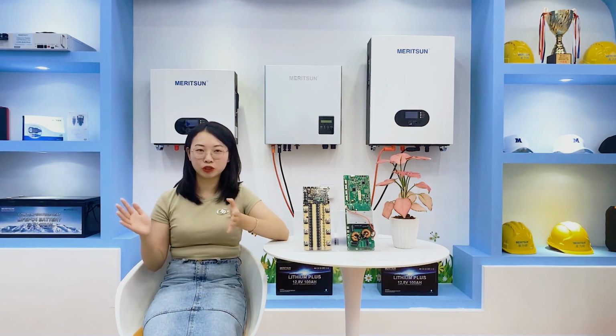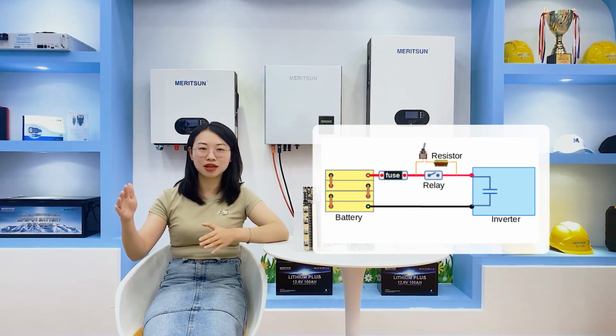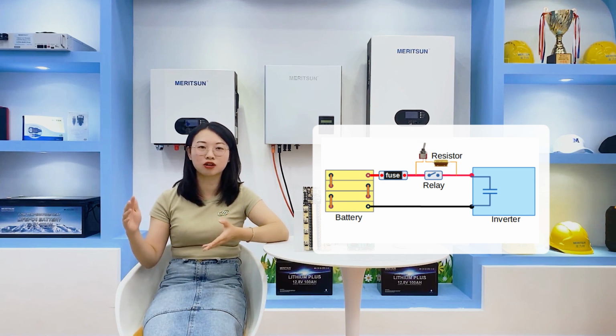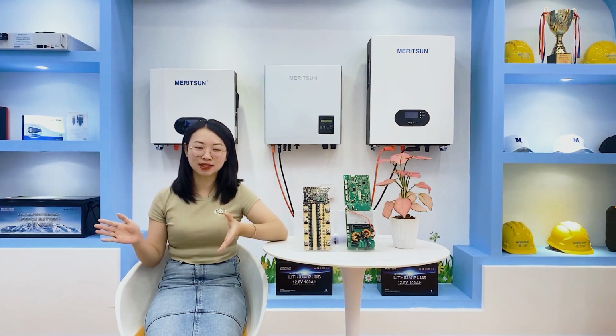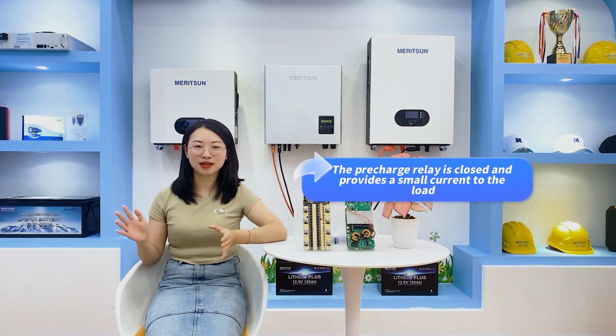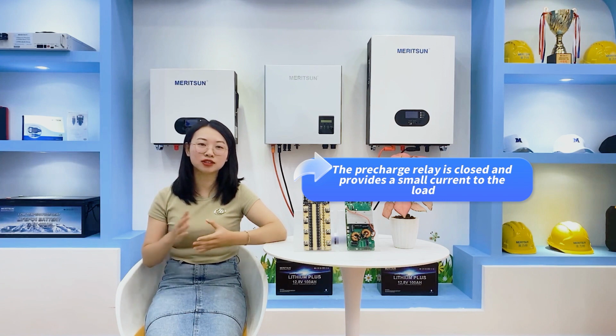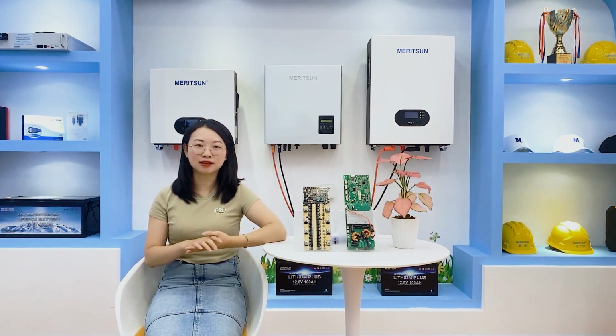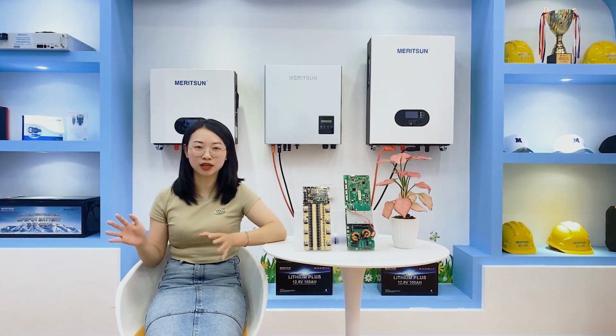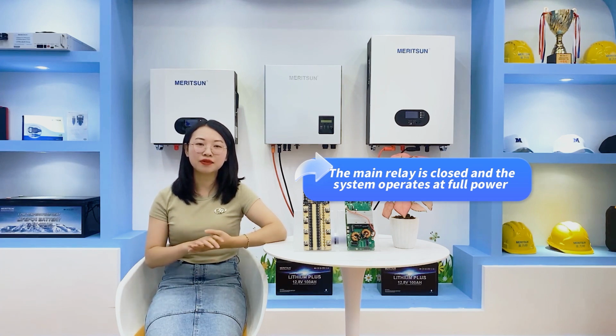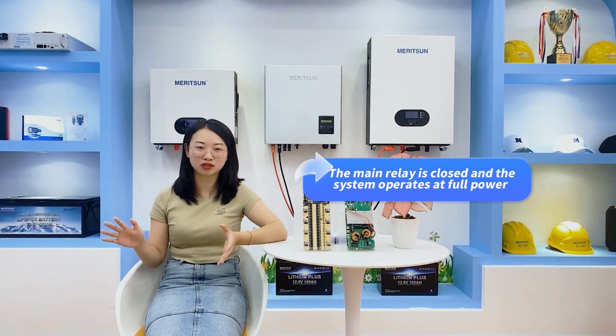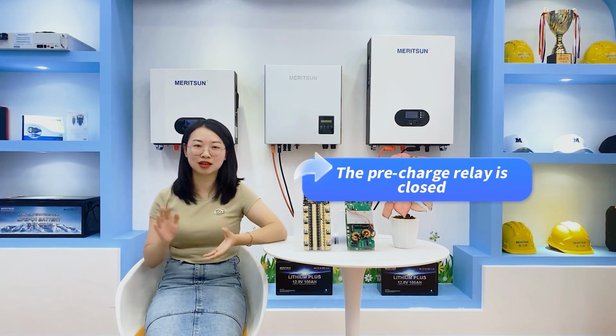In order to achieve pre-charge, we use a very simple and effective method: placing a small resistor in parallel with the relay contacts before closing the main relay, just like this diagram. Its working principle is like this. First, when the battery BMS activates the battery power, it initiates the closure of the pre-charge relay and offers a small current to charge the load. Second, as the voltage across the capacitor reaches 95% of the bus voltage, the main relay is closed, enabling the whole system to operate at full power. Finally, the pre-charge relay is opened.